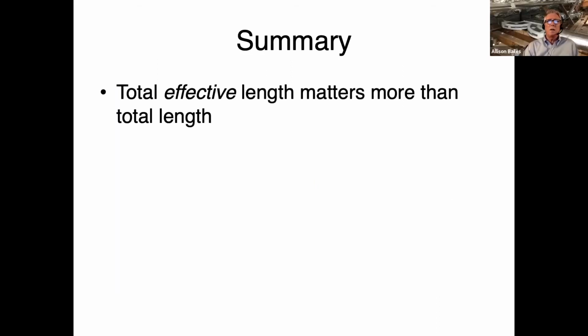Let's do a little summary here. Total effective length matters more than the total length. So myth number one is just not true. You can put long duct systems, a lot of ductwork, on low static air handlers. You just have to pay really close attention to the fittings, because that's where most of the resistance comes from, and the filters, because the available static pressure is the rated static pressure, like the 0.2, minus the pressure drops of the non-duct items like the filter and dampers and things like that.